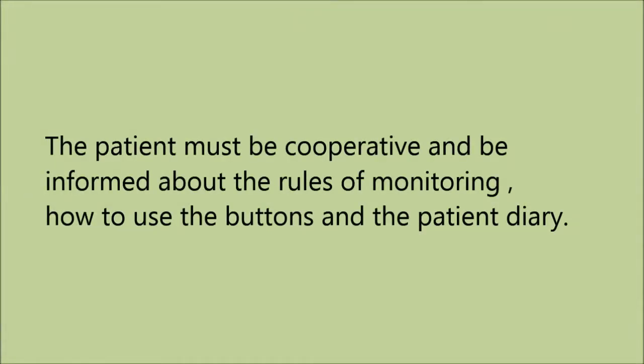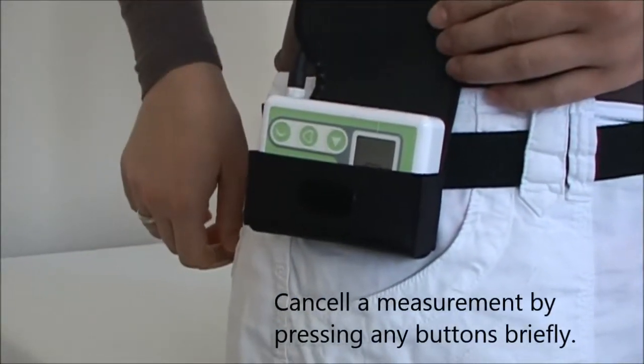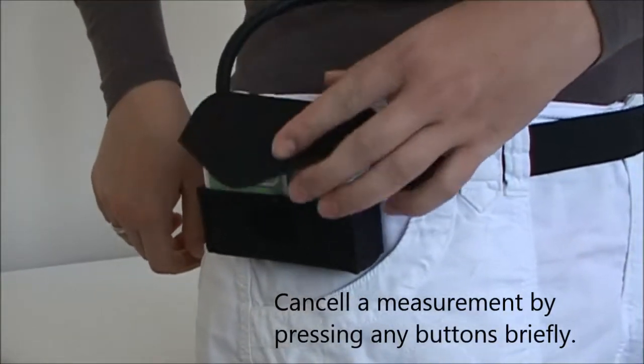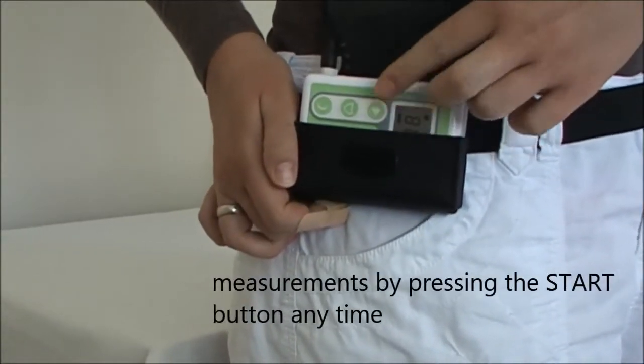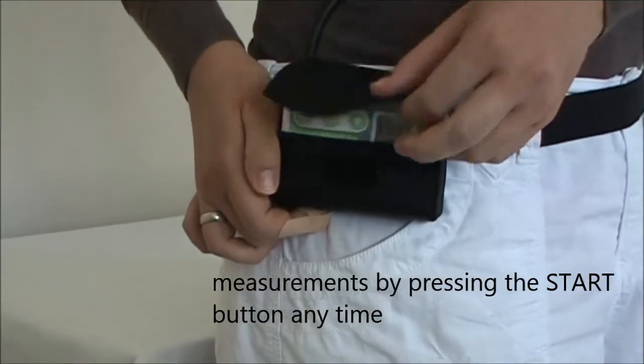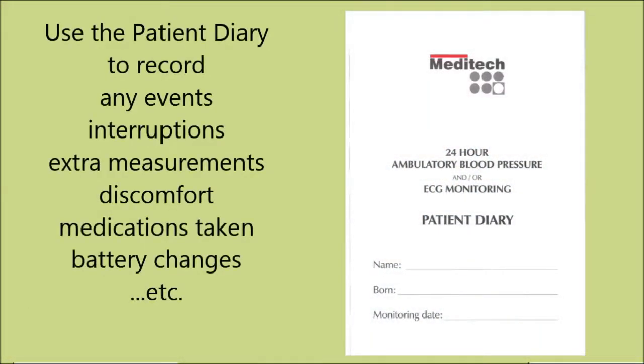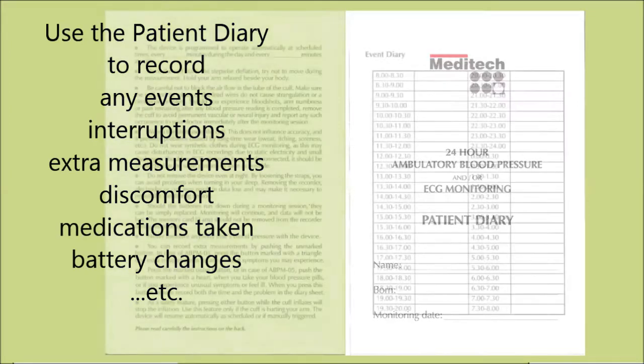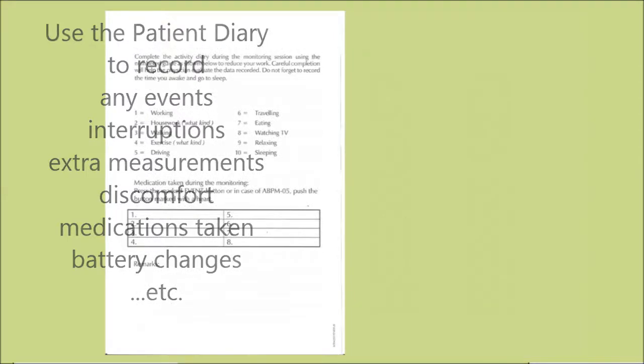The patient must be informed about the correct procedures during the monitoring, including using the patient diary. It is important that the patient knows how to cancel a measurement or initiate an extra measurement if needed. Apart from the patient diary, the device also has a journal feature which automatically stores recordings of events.